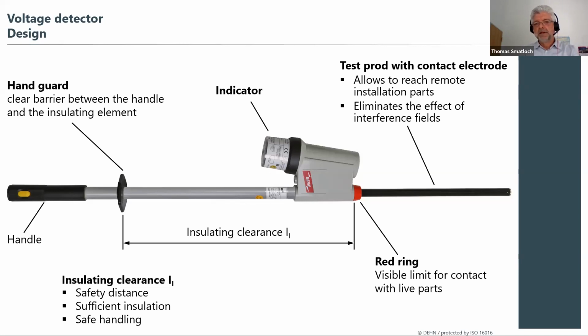On top of it, above the red ring, we have this test prod with a contact electrode, and this allows us to reach remote installation parts, of course. There are different prods available depending on the switchgear cabinet you are testing. The simple rule of thumb is that outdoor applications typically have longer distances, and therefore the prod is also longer in this case. For a lot of indoor applications, a shorter prod is typically in use. And the red ring, as I said before, is a visible limit for contact with live parts, of course.